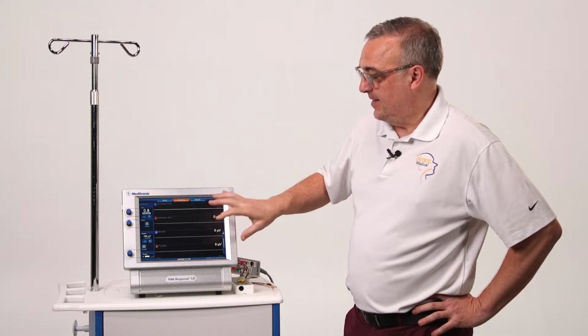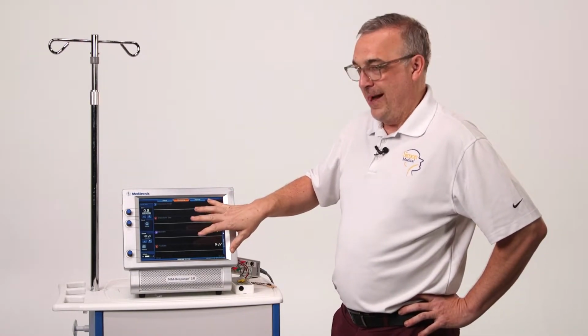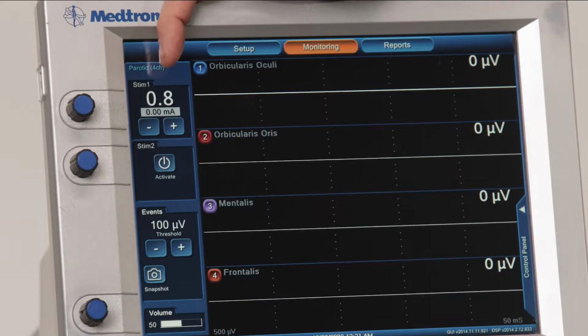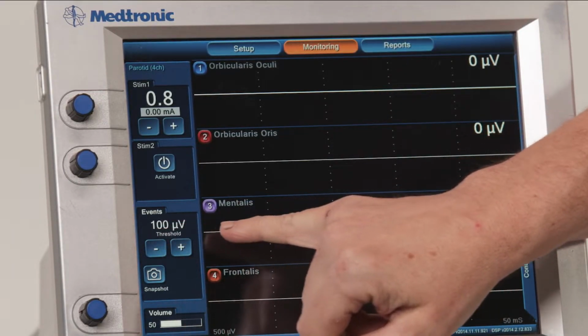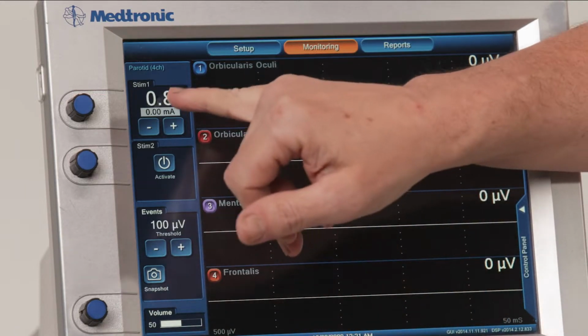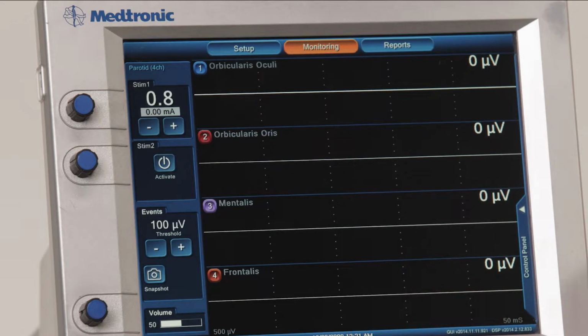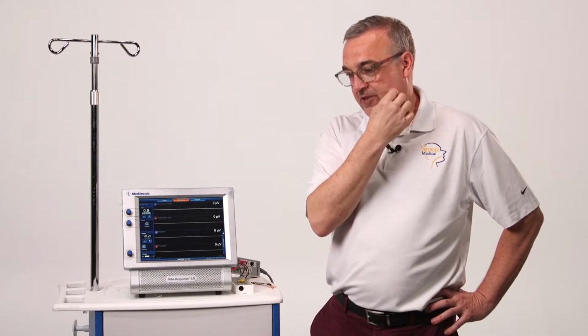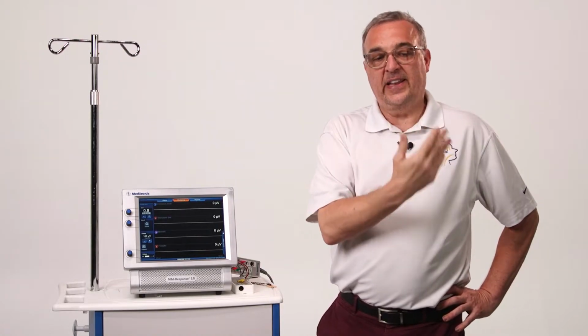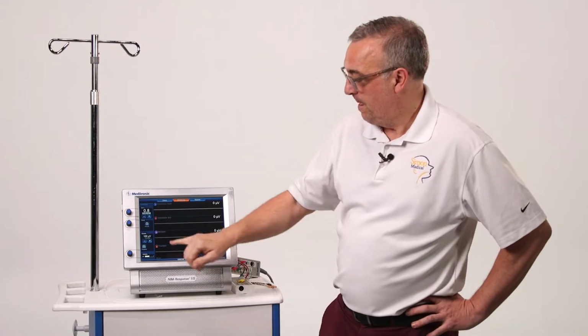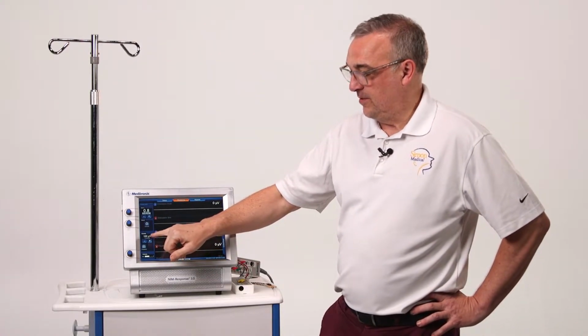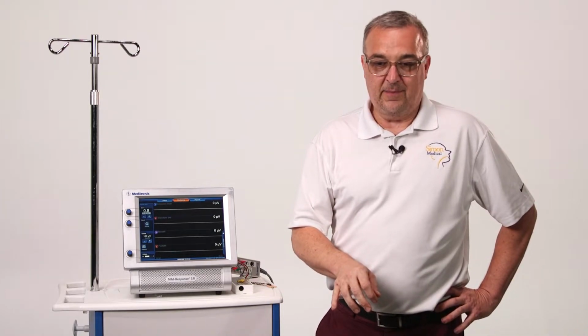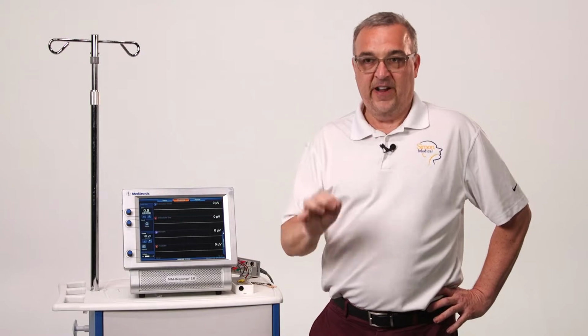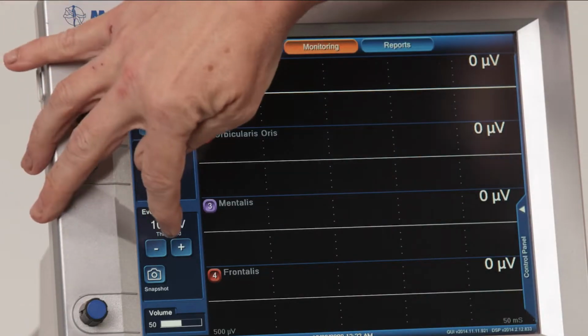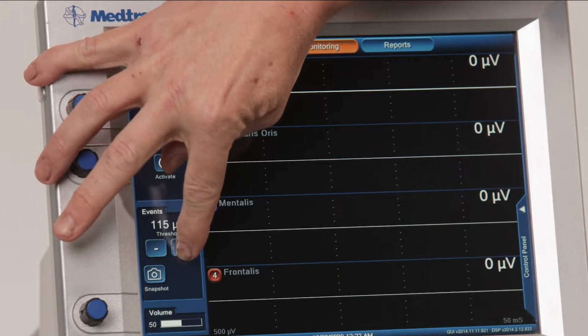This machine, when you pick that 4-channel setup or montage, is going to default to what we think is an appropriate setting, 0.8 milliamp stimulus and an event threshold of 100 microvolts. Okay, so that tells us when we stimulate in the site, if that electrode picks up an action potential, or that innervates that muscle, it's going to set off that alarm. Now, occasionally someone doesn't want it to be so sensitive, which is fine. Sometimes surgeons are like, I just want it to go off when I'm very close to the nerve. So you can increase, at the surgeon's discretion, the event threshold.